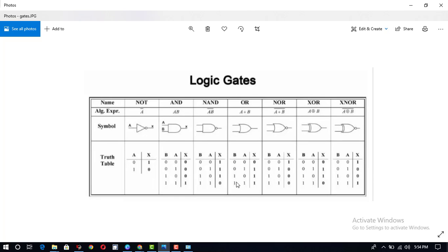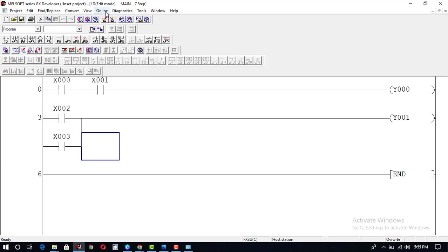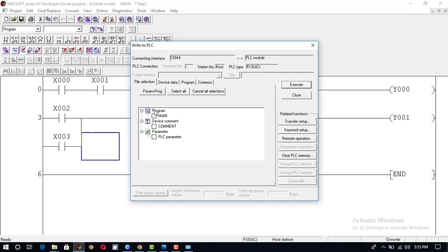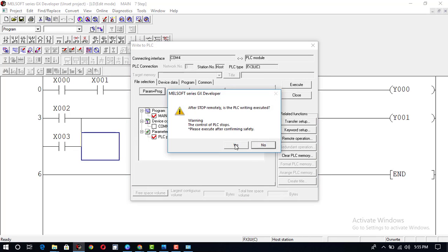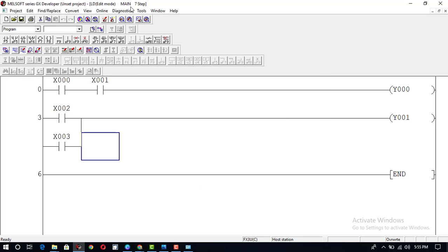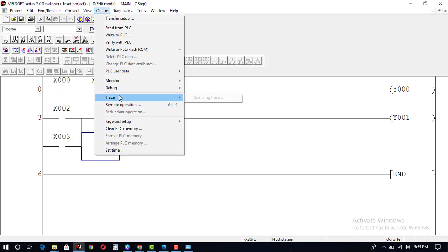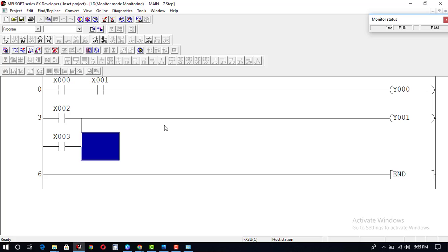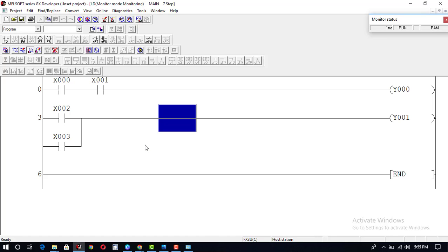Here is the OR gate truth table: if both inputs are 1, output is 1; if one of the inputs is 1, output will be 1; if both inputs are 0, output will be 0. We convert this program to ladder logic and go to Online, then write this program to PLC. The program is now loaded. In monitor mode we can check: if X2 is 1 output is 1, if X3 is 1 output is 1. This is the logic of the OR gate.